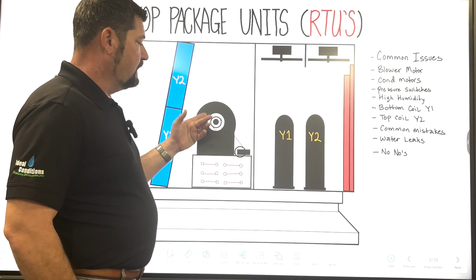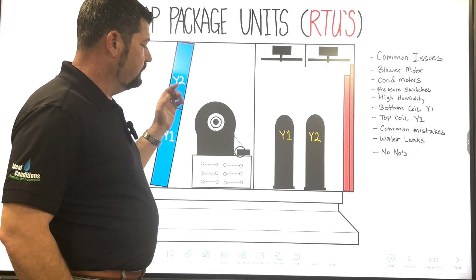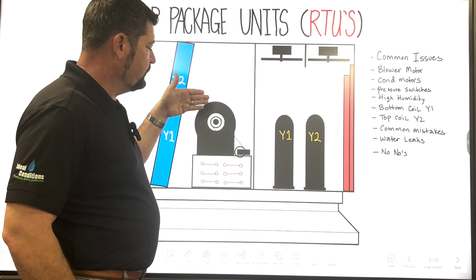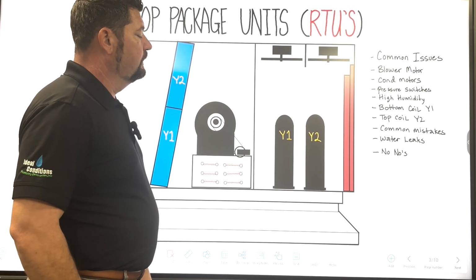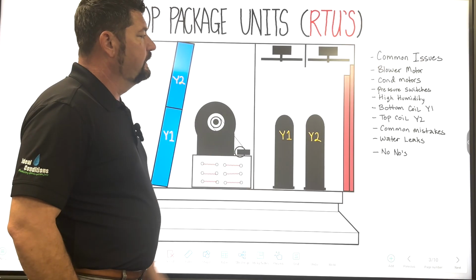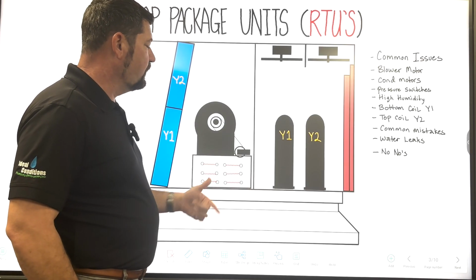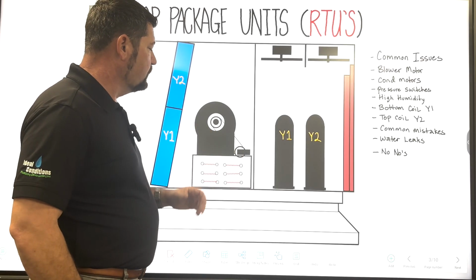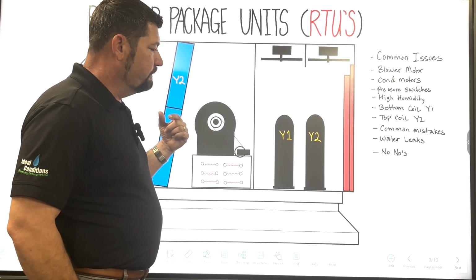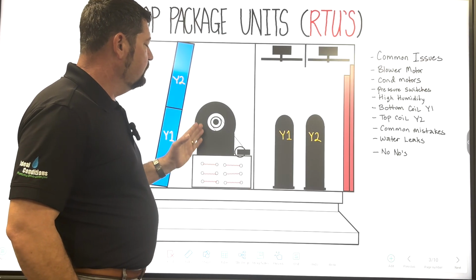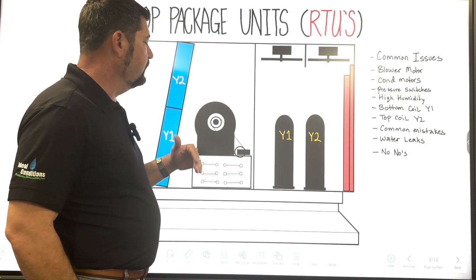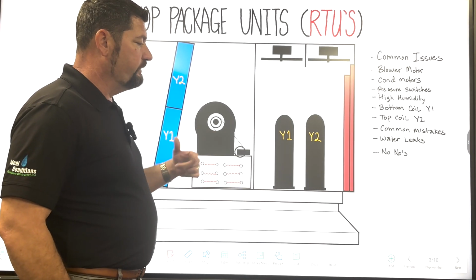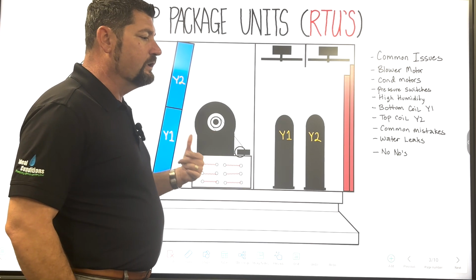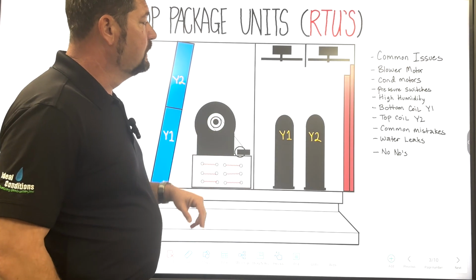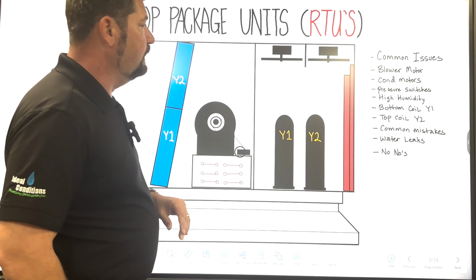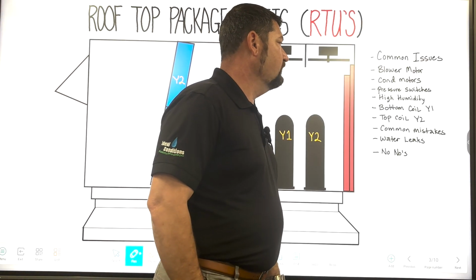These shafts, a lot of times there's little grease ports on them where you can take a grease tube and actually pump some grease into them to keep these bearings lubricated so they turn. As that shaft is turning because of the pulley and belt, the whole system is running. You want to make sure it's not causing any excess friction as a result of bearings seizing up, or the blower motor having too much vibration on it that could cause that wheel to separate. See that a lot too. So proper maintenance is key to these things functioning for the longevity that they were designed to function.